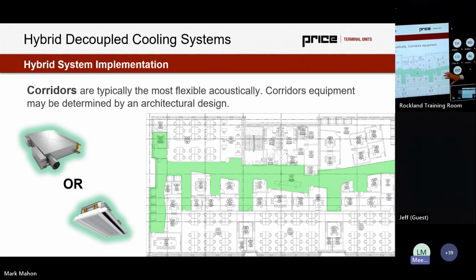Now, the corridors are always interesting. They're frequently acoustically flexible. They're often determined by architectural design, especially if they connect to potentially a larger atrium or lobby area. And this one, I'd be interested to know, does anyone have rationale for one or the other strongly? Fan-powered box or chilled beam, if we look at a corridor type space? What's your rationale for a chilled beam selection?